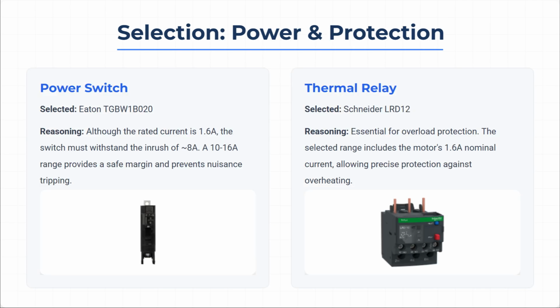Selection. Protection. We select an Eaton TGBW1B020 power breaker. Although the nominal motor current is 1.6 amperes, the breaker must withstand the inrush of 8 amperes. A range of 10 to 16 amperes provides a safe margin. For overload protection, we use a Schneider LRD12 thermal relay, essential for overheating protection, since its range includes the nominal current of 1.6 amperes.